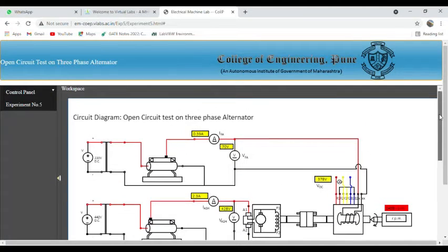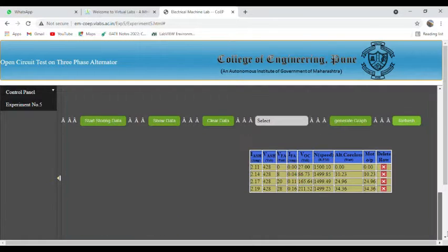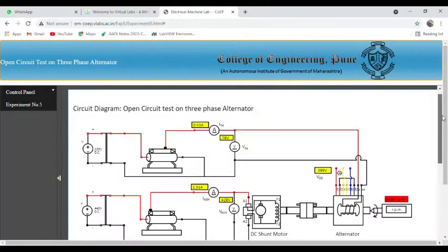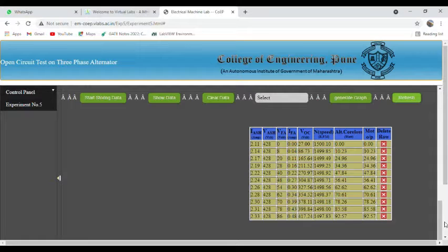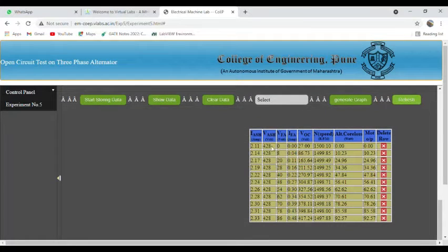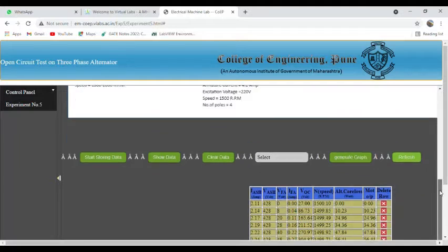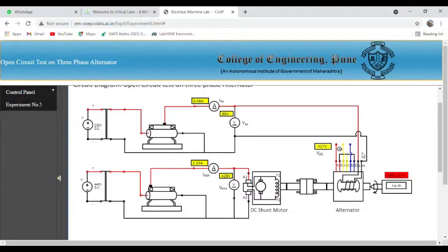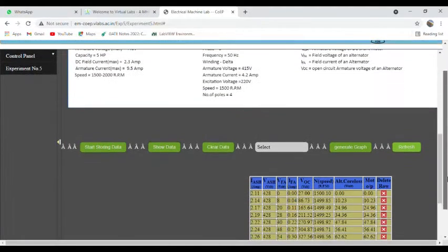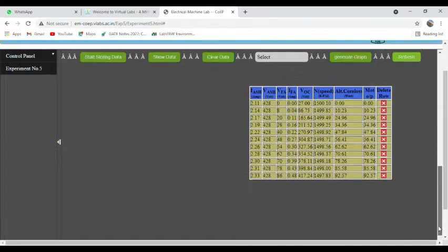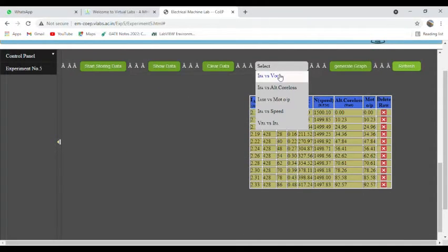The field current is varied in suitable steps and the corresponding values of the open circuit voltage across any two pairs of terminals of the armature winding are recorded. However, with progressive increase in DC field current, the flux will eventually reach a high enough value to saturate the iron in the alternator. Saturation in the iron means there will be a smaller increase of flux for a given increase in DC field current, because the generated voltage is directly related to the magnetic flux density.